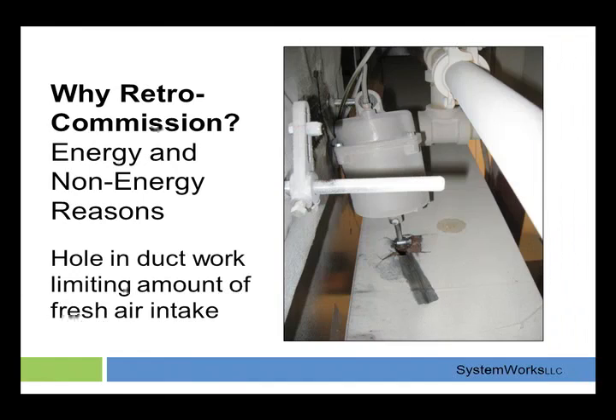Sure. The one in the middle actually shows an actuator. It's a pneumatic device that opens a damper to open the outside air for the return air. If you look at it, you can see that the connector that would connect to the jack shaft, which is standing right up next to the duct, has actually fallen off, and it's poking a hole in the duct below it. It's actually broken, and it's been broken so long it's actually punctured a hole in the ductwork.